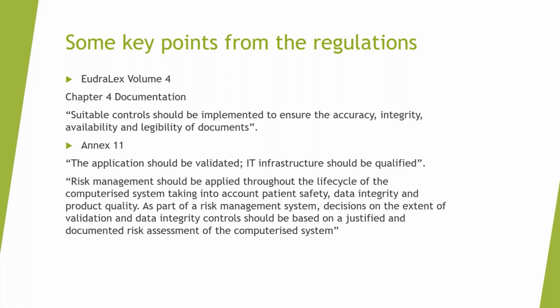Also, Annex 11 in EudraLex Volume 4 states that the application should be validated and that the IT infrastructure should be qualified. Risk management should be applied throughout the life cycle of the computerized system, taking into account patient safety, data integrity, and product quality. As part of the risk management system, decisions on the extent of validation and data integrity controls should be based on the justified and documented risk assessment of the computerized system.